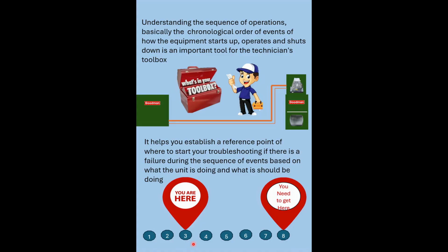What could cause this to happen? Because we need to get to 8. We're at 3. That's the question. What is it? And with furnaces, it could be water, an electrical issue of some kind, grounding. Grounding's huge. But you have to ask yourself what could cause that issue and rule it out.